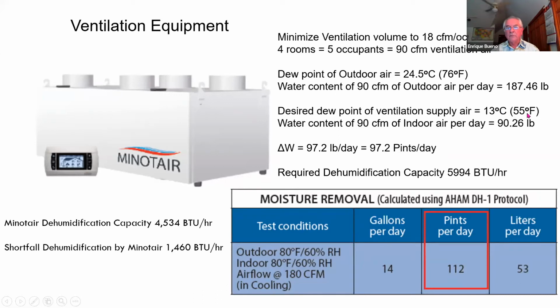This is according to Lou Harriman, the humidity guru here in the United States. So the water content of 90 CFM of indoor air per day would be 90.26. So the delta water then is 97.2 pounds per day, equals 97.2 pints per day. 1 pint is equal to 1 pound. So at first glance, the Minotair with 112 pints per day seems okay.